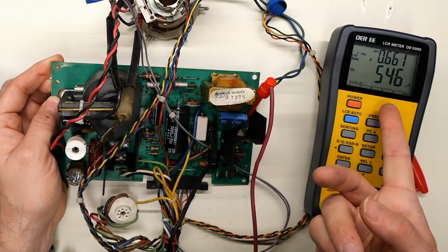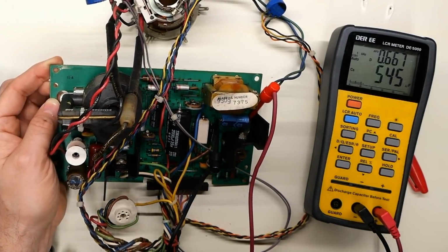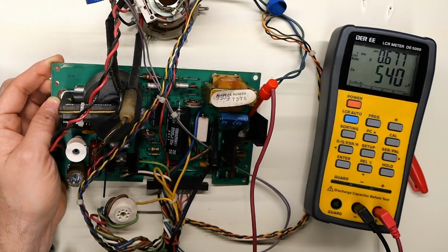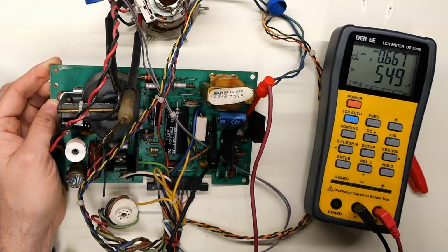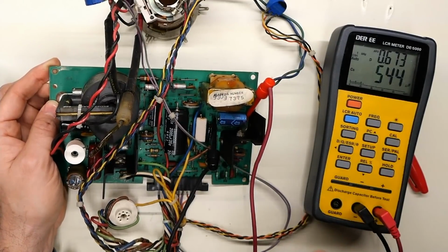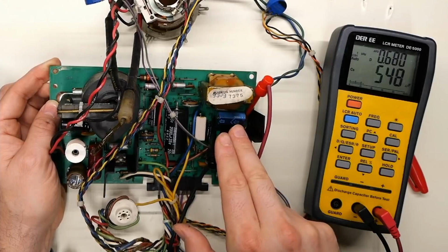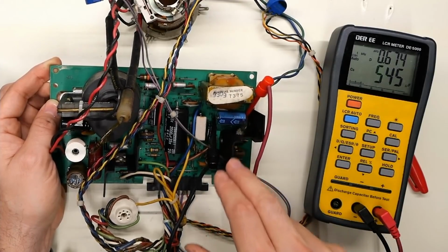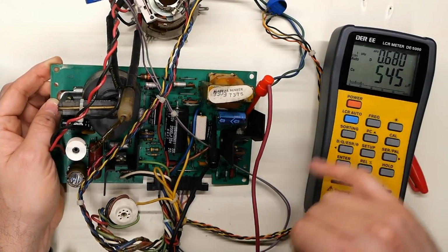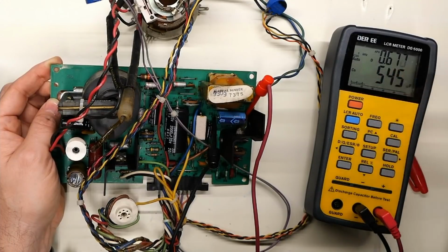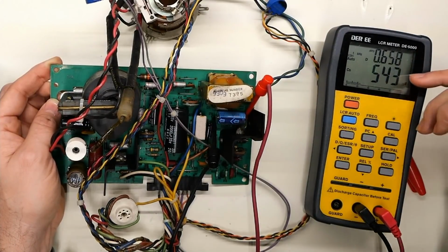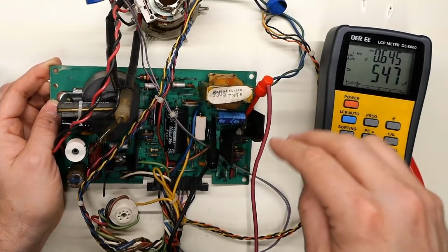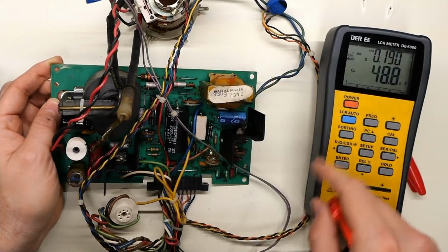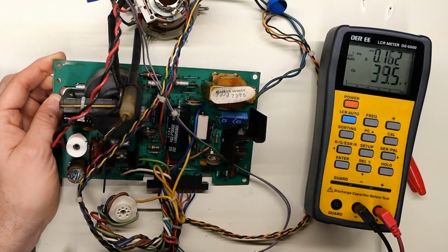We get 546 microfarad, and I can see that it's rated 470 at 16 volts. Now it's reading a little bit high, but that could be because of age, or it could be because there's stuff in parallel to that. It doesn't look too bad, and the D value, which is 0.67, seems okay as well. If the D value were very high, then I'd be concerned, like if the number was 3 or 4 or something like that.